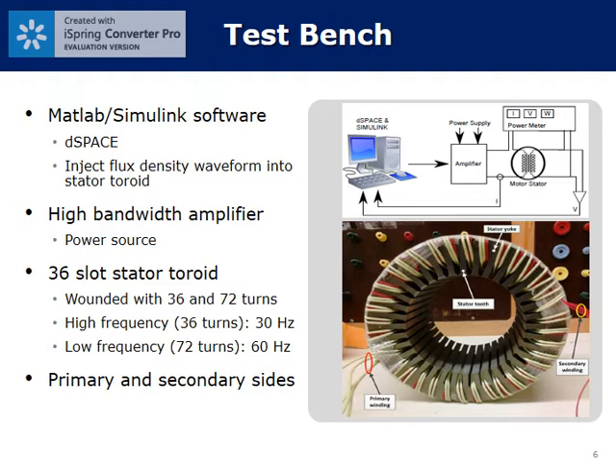And core loss measurement is really a product of the current on the primary with the voltage on the secondary. That gives you the losses of the core. It's a standard measure of losses. So it's a 36 slot stator toroid. We had different turns for different frequencies. For example, we can't do 60 hertz with 36 turns. So we increased the turns to 72 turns to be able to go to 60 hertz. Otherwise, you get core saturation.